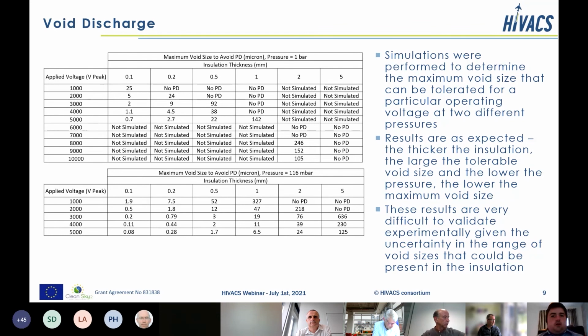In the table, there's some results that says no PD, and what this means is that the void size required for PD is bigger than the insulation thickness. So effectively, you would have no insulation between the conductor or the conductor screen and the insulation screen. So effectively there you would be looking at a full breakdown in the air gap. So this is therefore a different phenomena altogether. Insulation thickness and the pressure both have an impact on the void size that you can tolerate, depending on the voltage as well.